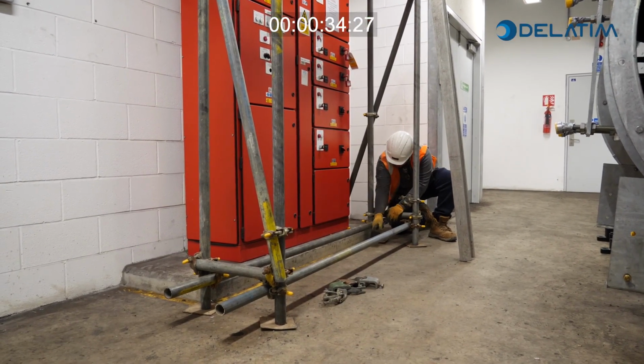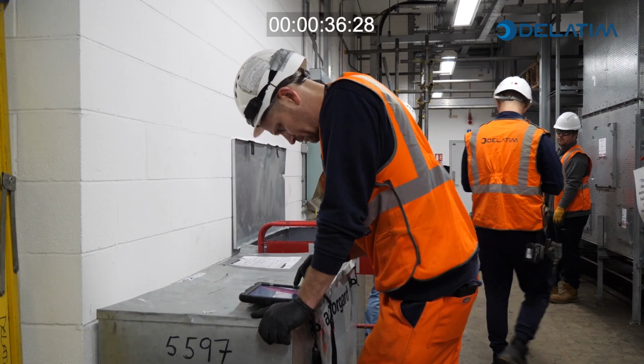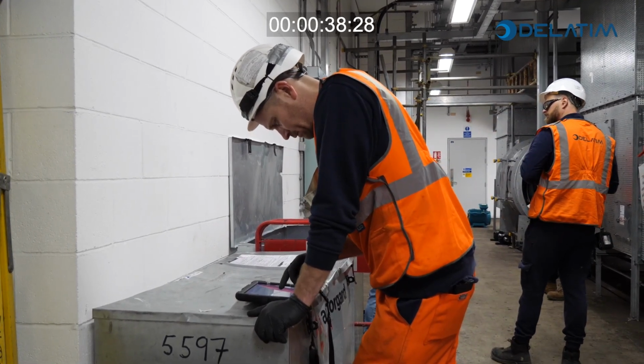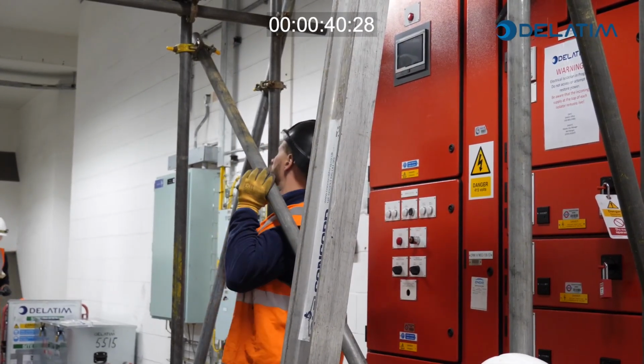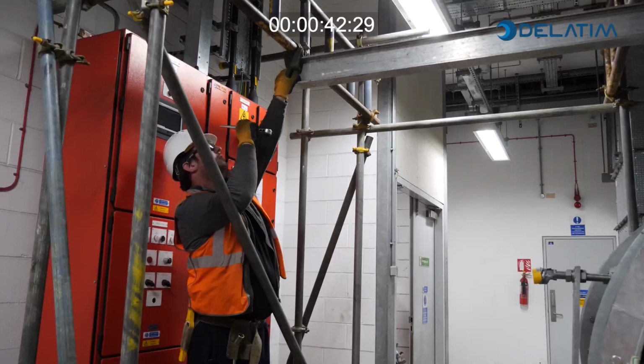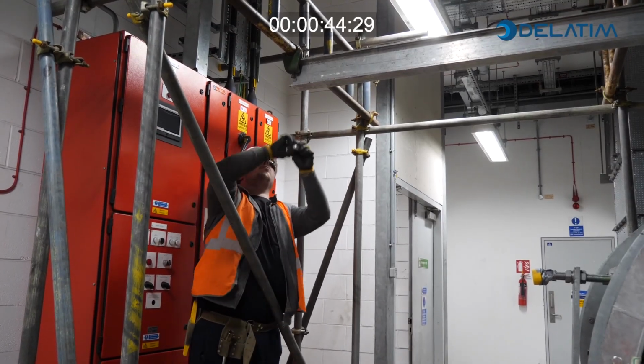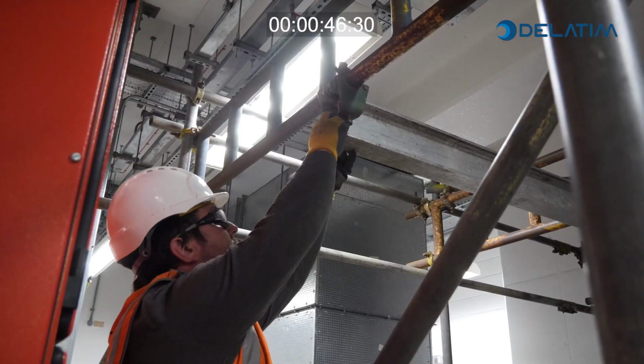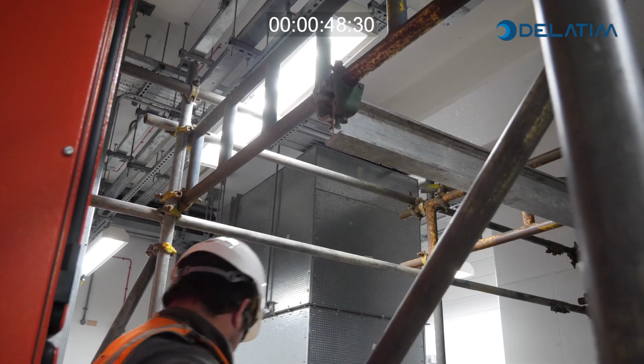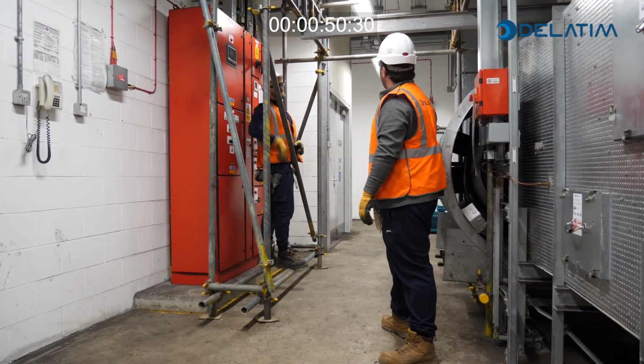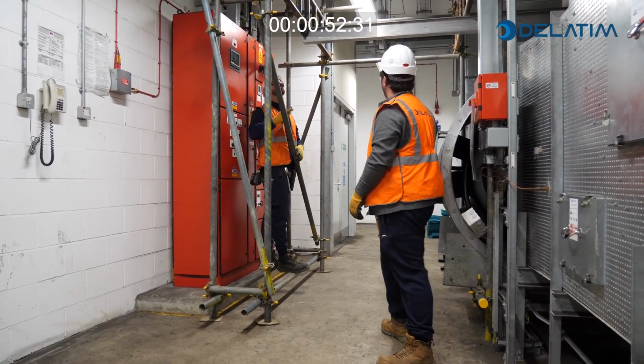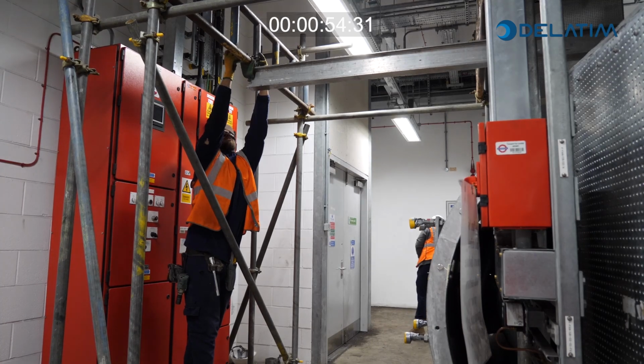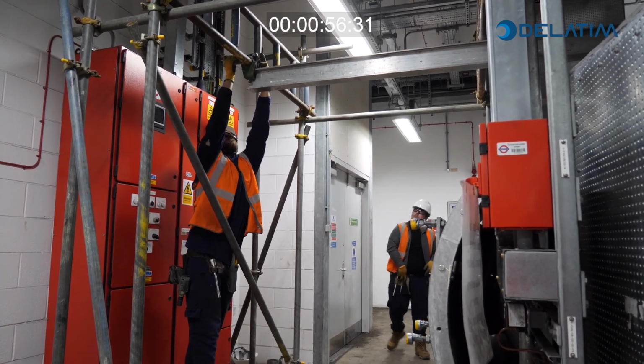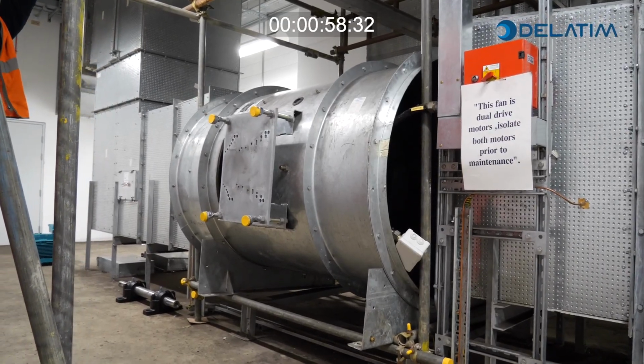Each pressurisation system is designed to prevent smoke from entering into the escape staircases as well as lifts. This is to enable safe passenger egress and a place of safety for London Fire Brigade to tackle a fire in that scenario. The majority of these systems were originally commissioned in and around 1999 for the Jubilee Line extension.